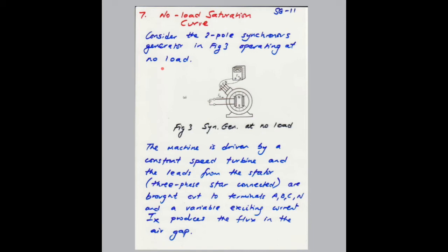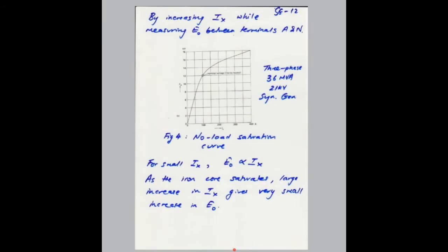There's no load connected to the machine, and the field current produces the flux in the air gap, right? And as we increase the field current, you can see that the voltage induced between the line and the neutral starts to increase. So in the initial stage, as you increase the current from, for example, 0 to 100 amps in this machine, which is rated at 36 MVA and 21 kV, right? So that's the three-phase power rating of the machine, and that's the line-to-line rating of the machine, right?